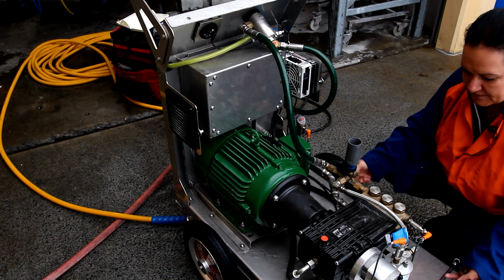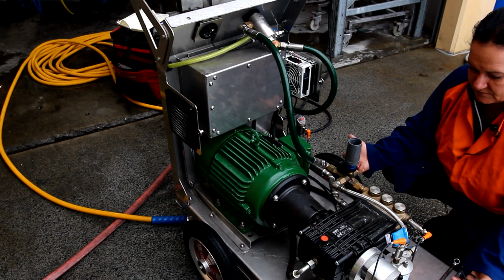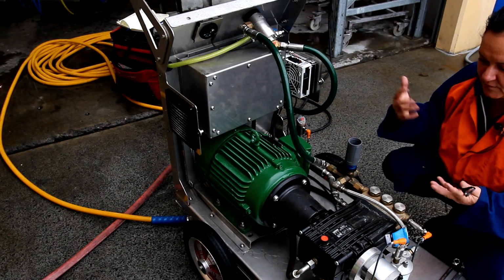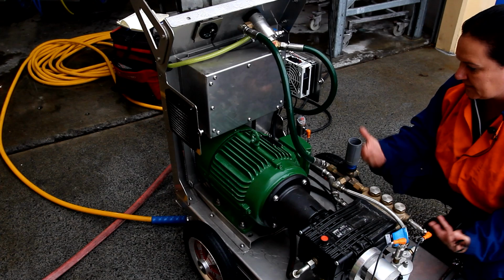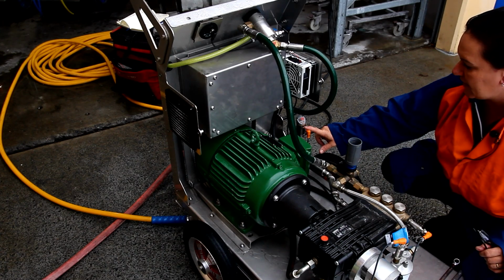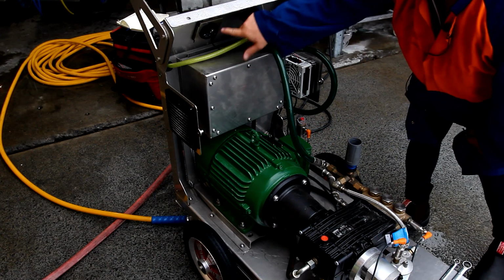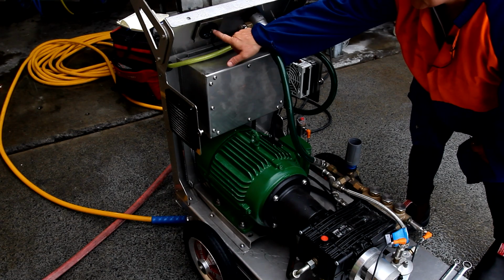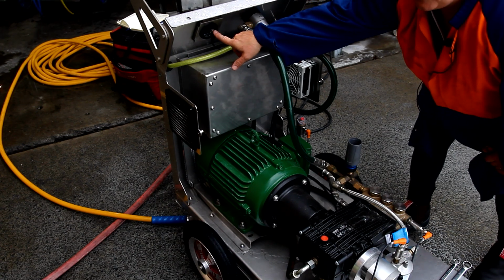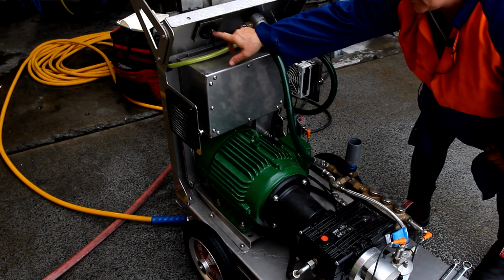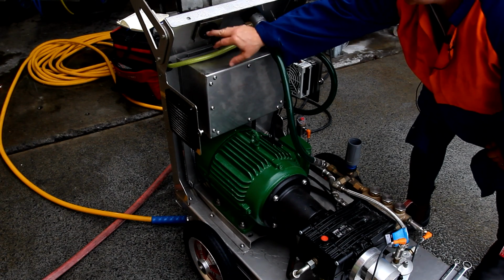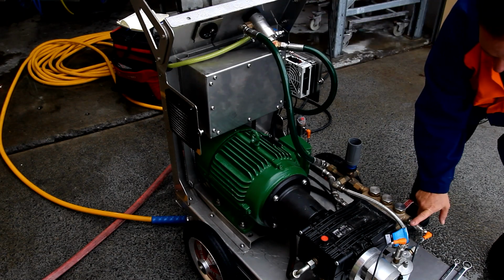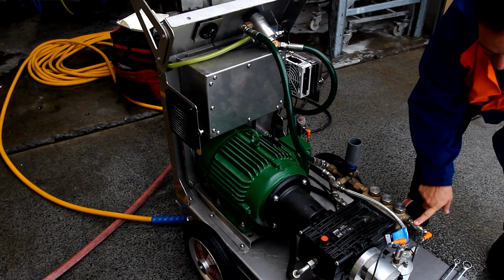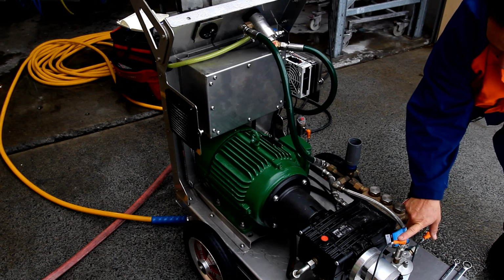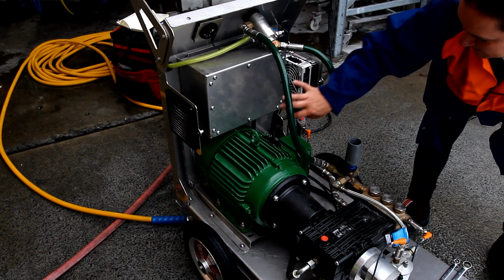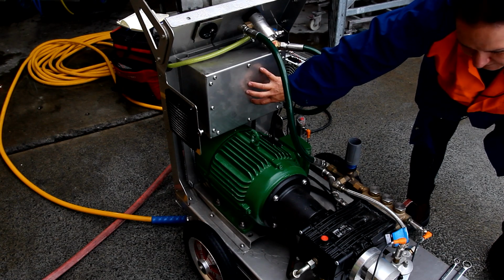According to where it's connected, you're going to have issues depending which electrical we're set up with, whether it's WEG or IFM. They'll be slightly different, but basically if the connection is loose, it won't work. So we have the connection at the flow sensor. We have the connection between the PLC and the HMI. We'll do further training videos on a separate time on the actual PLC and what's in this electrical box. So there's that one there. Then we've got the water pressure sensor, and then we have our oil sensor as well. We want to make sure all of our electrical connections are intact, and this is dry. That sort of covers electrical.